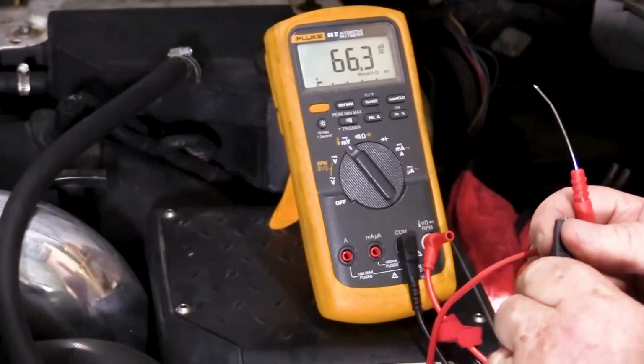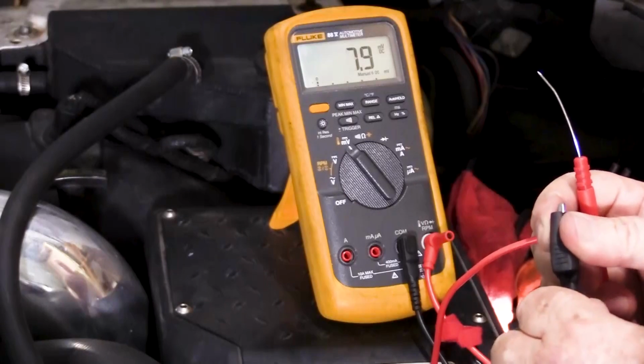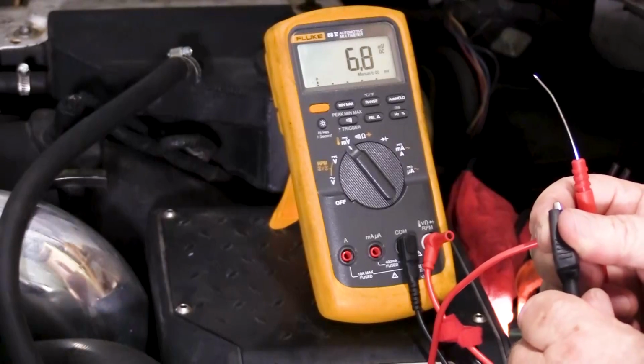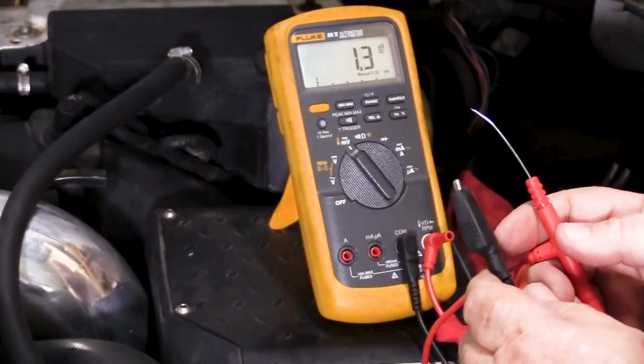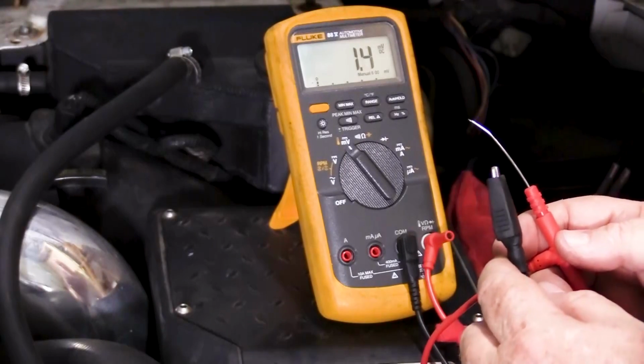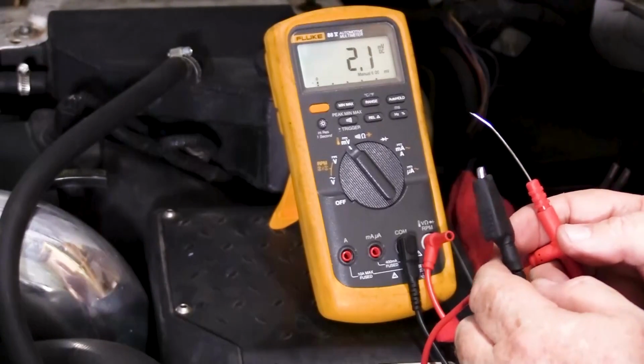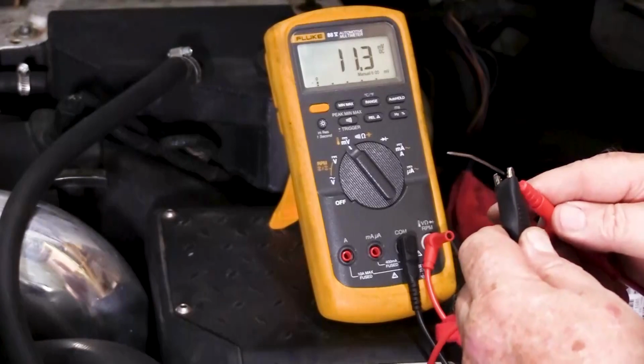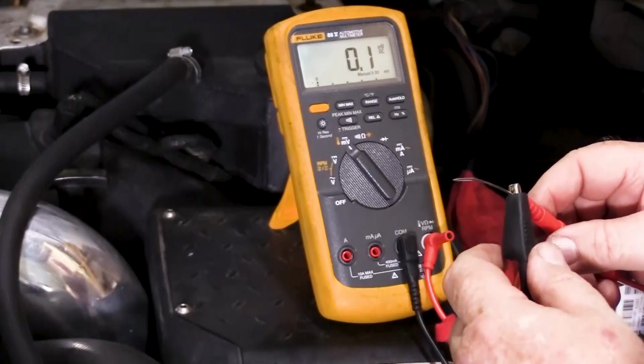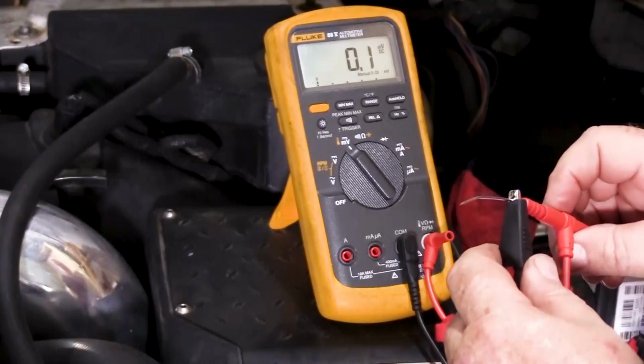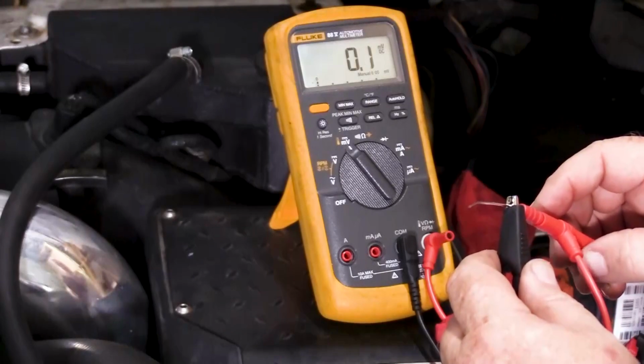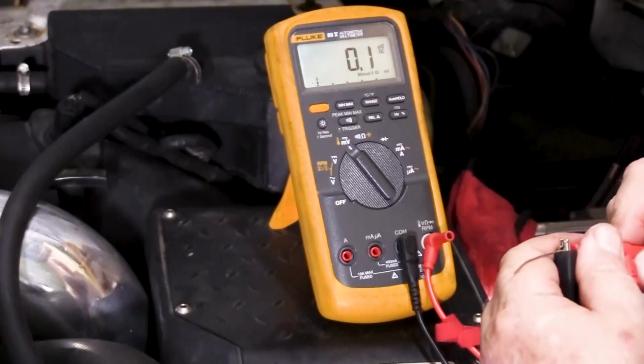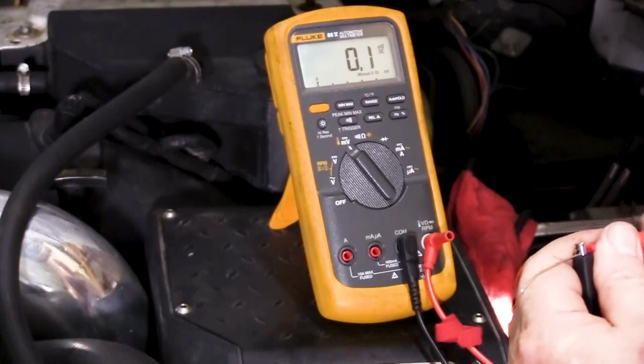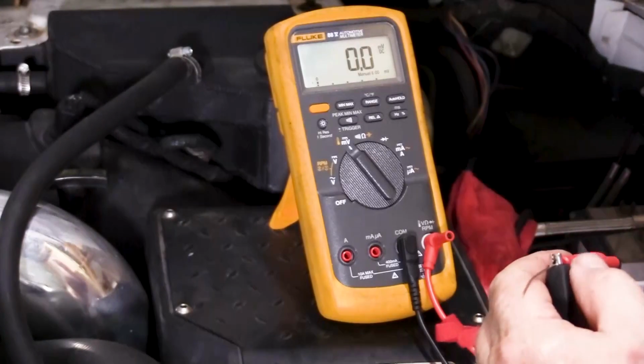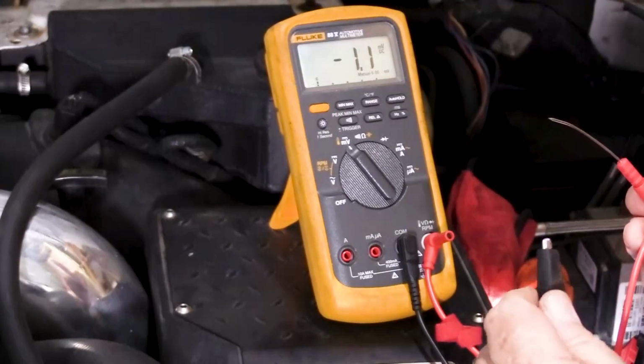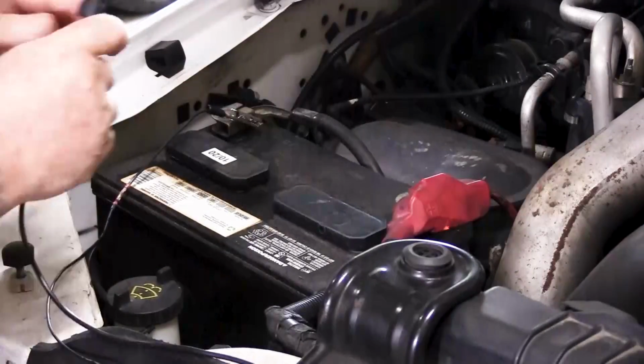When you hold a lead in each hand, you may see the reading on your meter bounce around and not stabilize. This is ghost voltage, and it lets you know that your leads are not making good contact. Touch the leads together and the bounce should disappear, replaced by a perfect zero reading. Now I know the leads are properly connected, and any reading I get that remains stable can be counted on as a good reading. Back to the test.